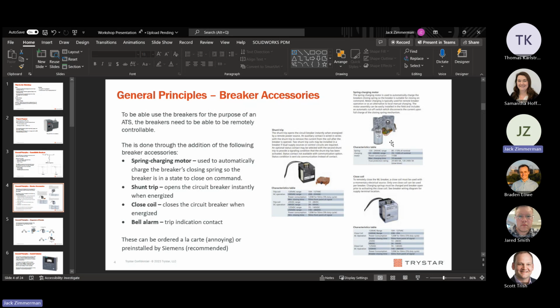As well as that, there's the close coil, which is like the shunt trip, but the opposite. It closes the breaker when energized. One thing to note about these is that they don't use a ton of power, but when they are using the power, it's a decent amount. So it's only like 50 milliseconds of runtime, but I recorded up to 150 watts per little accessory, which is quite substantial, especially if you're using power through a power supply, which a lot of our power supplies only do 240 watts total or 480. So definitely something to consider there.